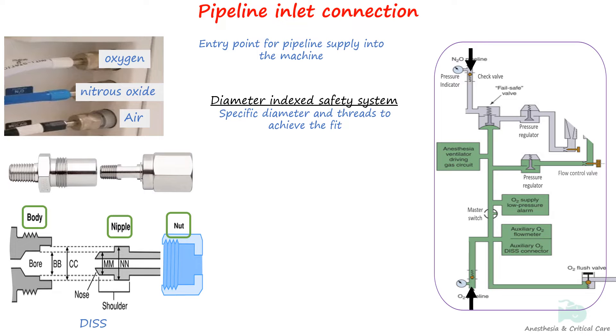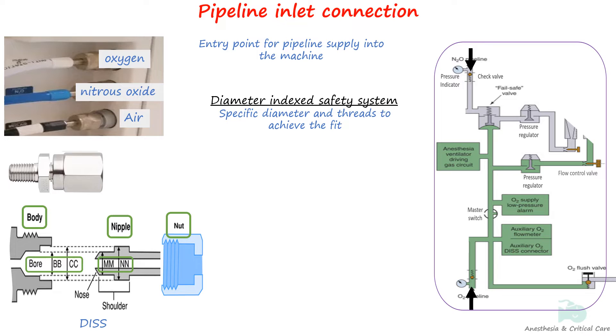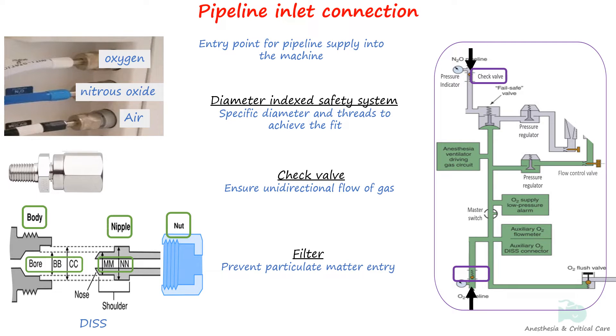Two concentric bores, BB and CC, on the body fit into two shoulders, MM and NN, on the nipple. Only when these parts align can the threads of the nut and body engage securely. The inlet connection is fitted with a check valve — like the high-pressure cylinder system — to prevent reverse flow of gas from the machine to the pipeline system. The pipeline also has filters of 100 micrometers to filter the gas.